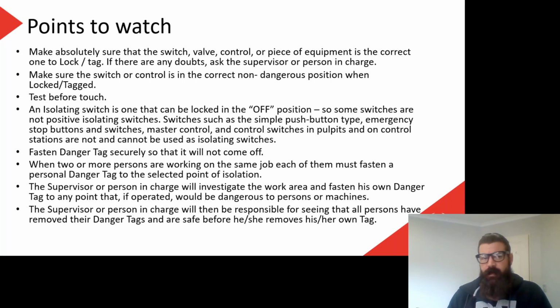Test before touch. So test before touch means, in addition to our prove, test, prove, sometimes we'll just do a quick test. If I've isolated a whole machine and I've tested that the supply to that machine is off, every now and then, if I move from one part of the machine to another, I might just do another test before touch, just to make sure that there's nothing else going on. There isn't a second source of supply coming in or something like that. So test before touch is an important one as well.